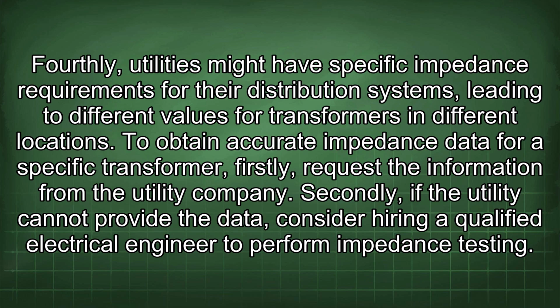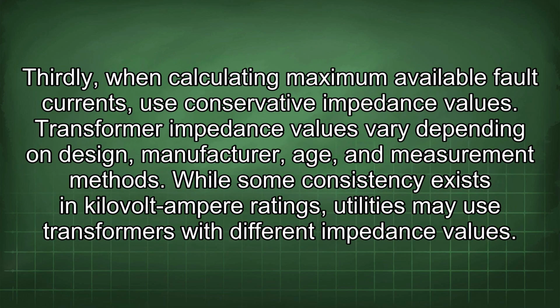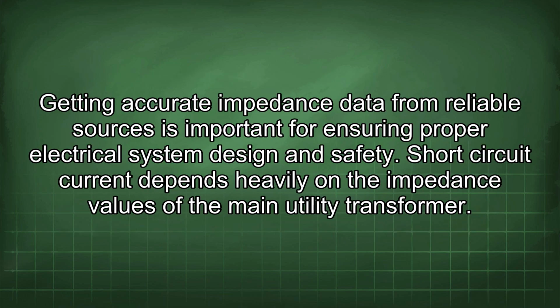To obtain accurate impedance data for a specific transformer, firstly, request the information from the utility company. Secondly, if the utility cannot provide the data, consider hiring a qualified electrical engineer to perform impedance testing. Thirdly, when calculating maximum available fault currents, use conservative impedance values. Transformer impedance values vary depending on design, manufacturer, age, and measurement methods. While some consistency exists in kilovolt-ampere ratings, utilities may use transformers with different impedance values. Getting accurate impedance data from reliable sources is important for ensuring proper electrical system design and safety.